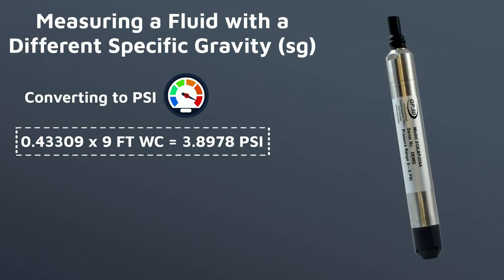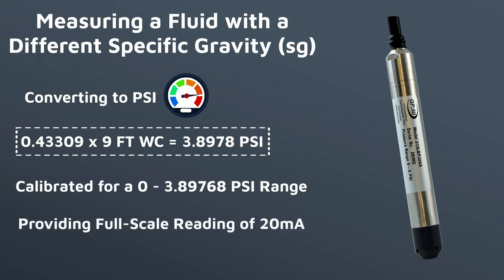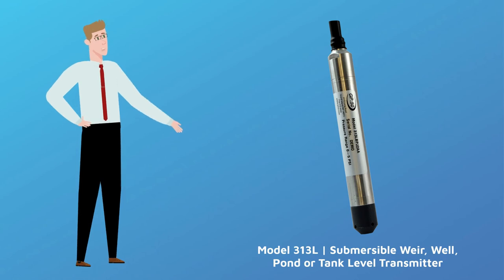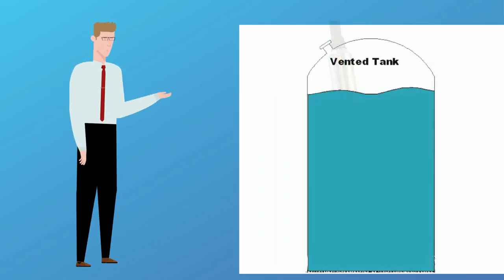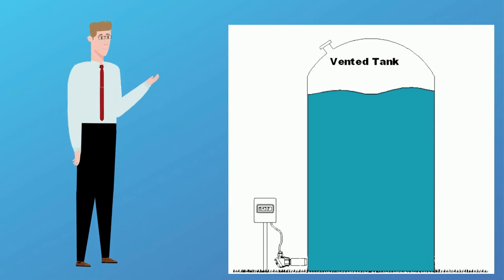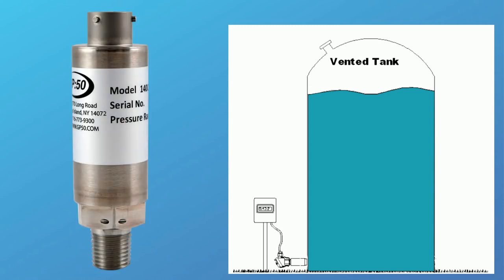The level transmitter will then be calibrated for a 0 to 3.89 psi range and provide a full scale reading of 20 milliamps when the tank of oil is full. This example uses a submersible level transmitter. However, you can also install a pressure transmitter outside the tank wall via a feed-through fitting at the base of the tank. Once the transmitter's process port is installed on the feed-through line, it will sense the head pressure in the same way the submersible transmitter does and provide a head pressure reading.